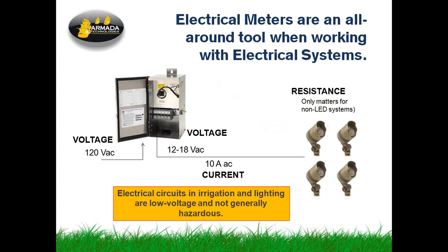When you're dealing with lighting systems, the voltage is even lower, 12 to 18 volts, and 10 amps AC is common in a system, much larger current, easily measured with a clamp. If you have an incandescent lighting system, the Pro90 does a good, accurate job of measuring the amount of power being delivered downstream. In an LED system, you really need to use a Pro91.